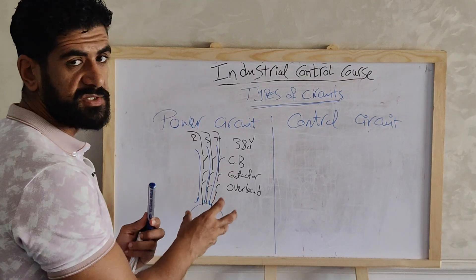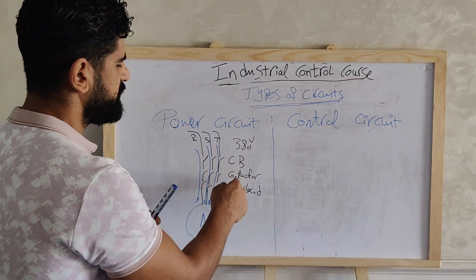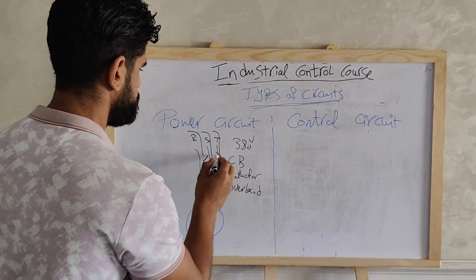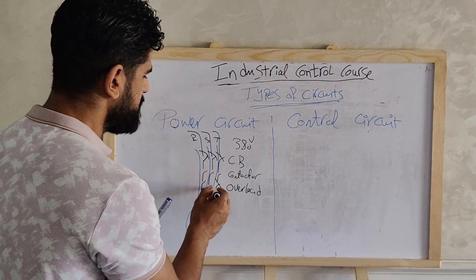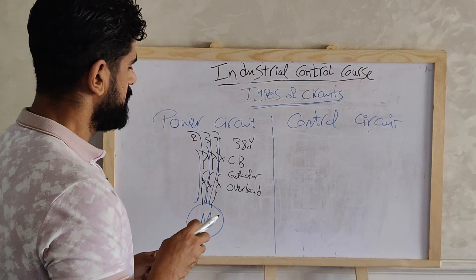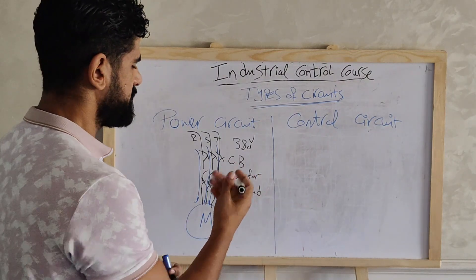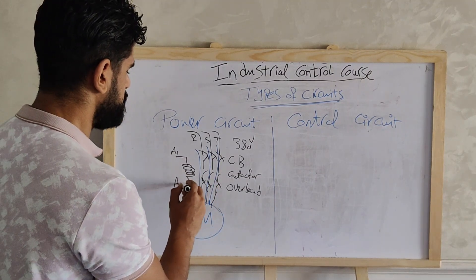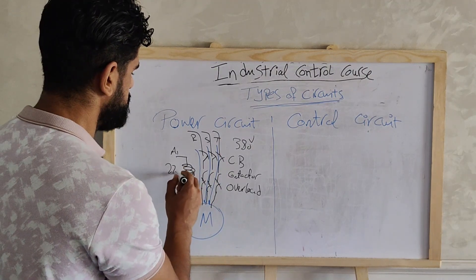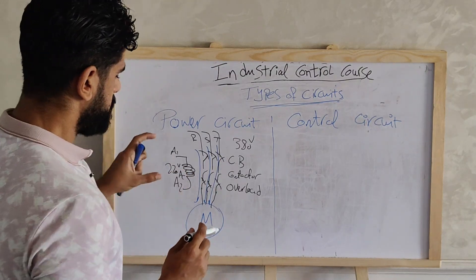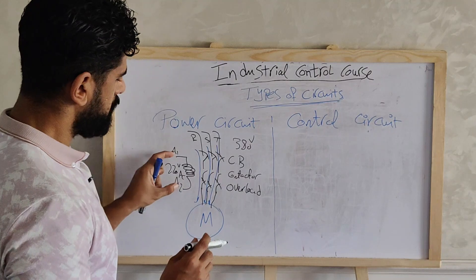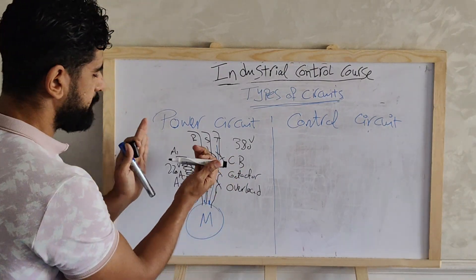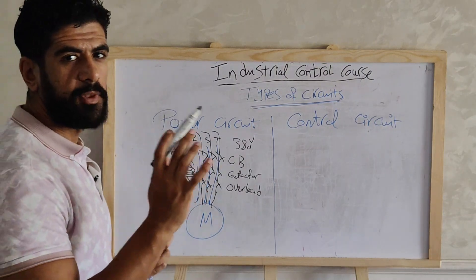To make the motor work we need the circuit breaker, contactor, and overload to all be turned on. The circuit breaker is closed manually. The overload has normally closed contacts. But the contactor is normally open, so to make it work we need to energize its coil by applying a rated voltage — typically 220V AC. When 220V AC is applied to the coil the contactor turns on and current flows to make the motor rotate. This voltage is applied via the control circuit.